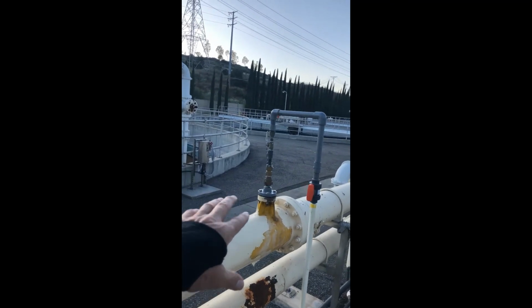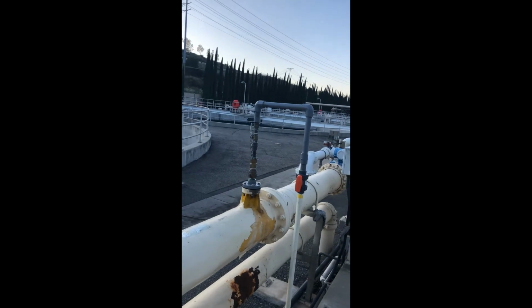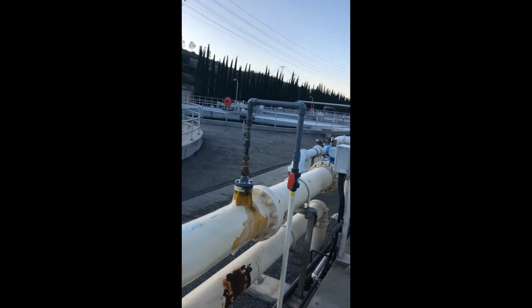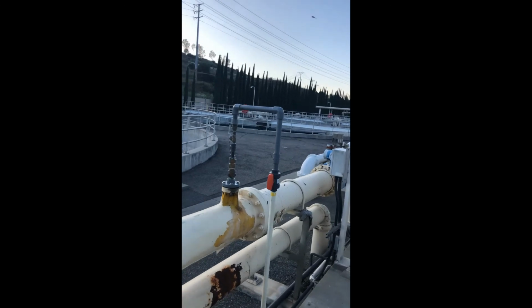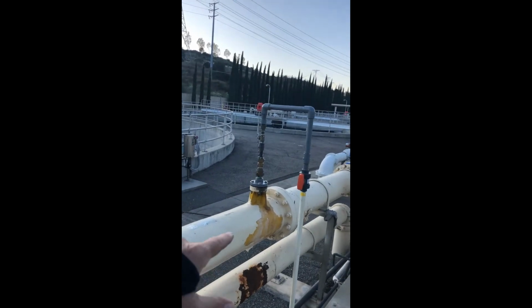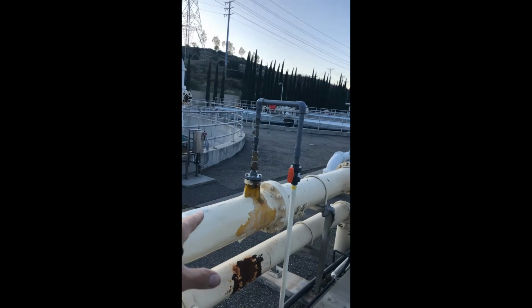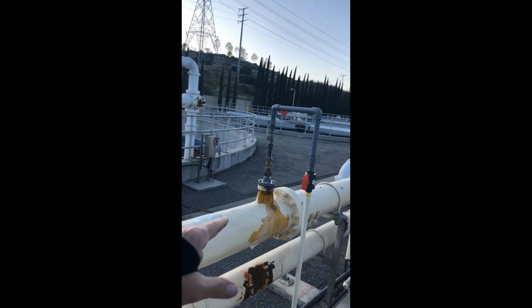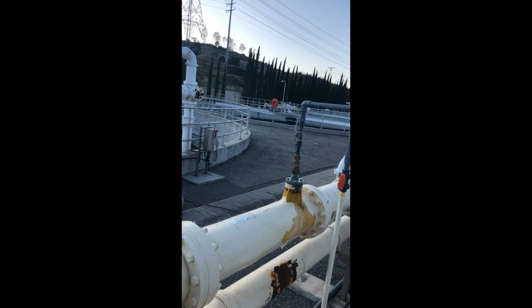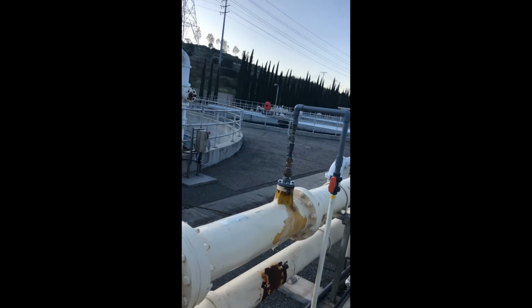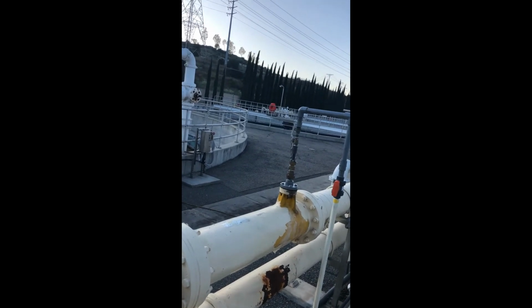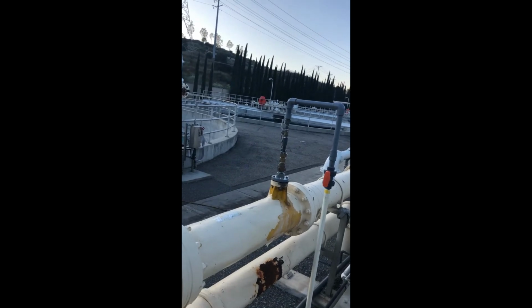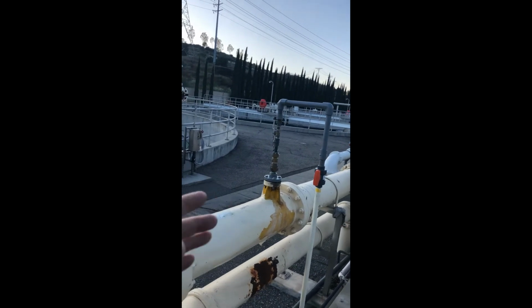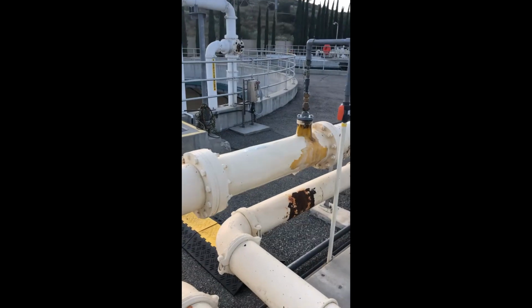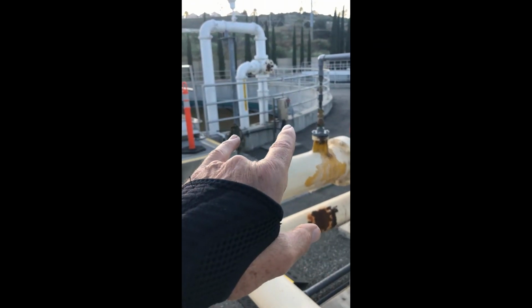And it's an open loop control because we're not looking at the chlorine residual meter. It takes too much time for it to react, and it's just not a feasible way of doing it. But on our open loop controls, we have a gain adjustment on the SCADA screen where they can look at the residual and say, you know what, the chlorine demand is kind of high. We're going to dose it a little bit harder, give a little more chlorine proportionally to how much flow is coming through.